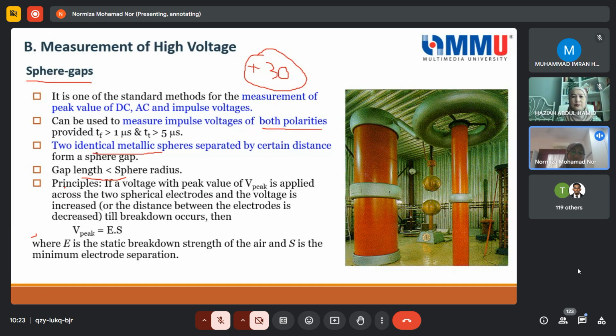Okay, so the principle is that a voltage with peak value is applied across the two spherical electrodes, and the voltage is increased, or the distance between the electrodes is decreased, until breakdown occurs. So when we apply, for example, 150 kV, then of course we have to adjust this gap so that it gives breakdown at close to that 150 kV.